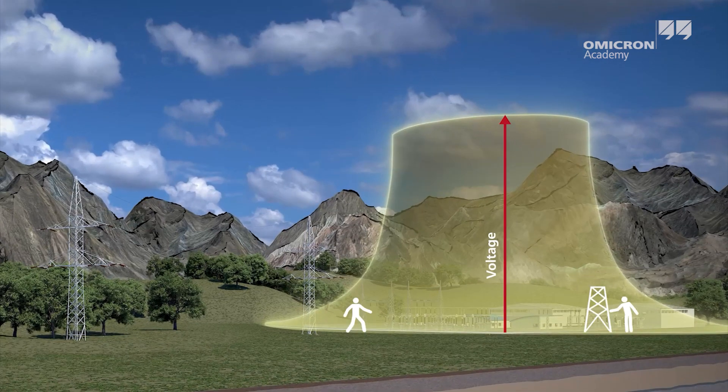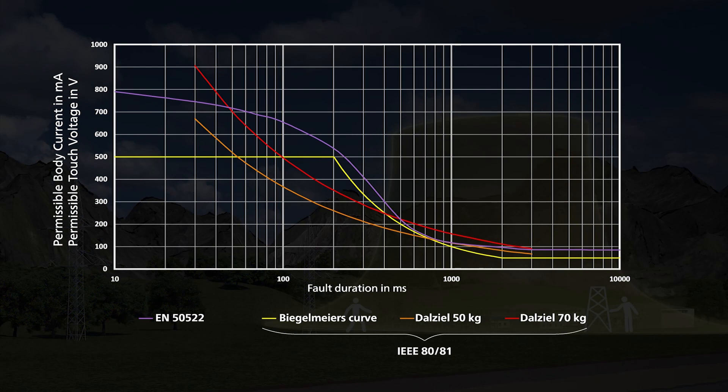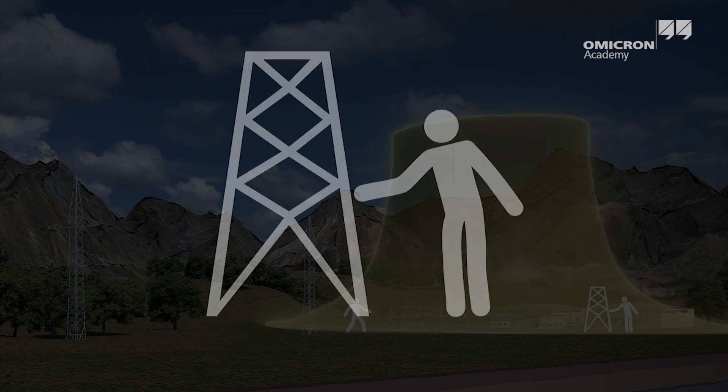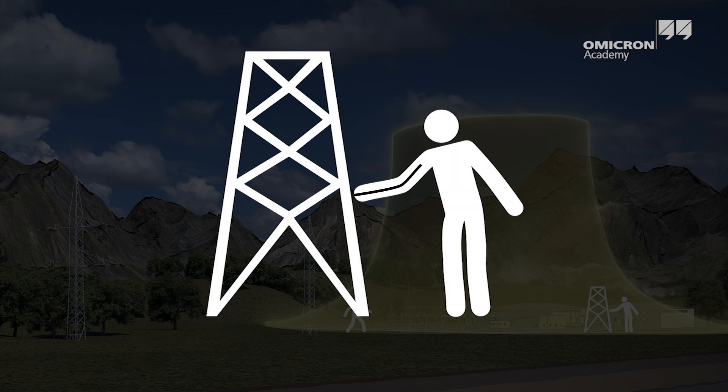This potential rise leads to different step and touch voltages. Their amplitudes depend on the distance to the grounding system and the properties of the soil. These voltages can cause harmful or even lethal currents in the body. Applicable medium and high voltage standards like the IEEE 80/81 or the European standard 50522 therefore define the maximum permissible step and touch voltages. Touch voltages are in general even more important than step voltages, as the resulting current will flow via the heart.